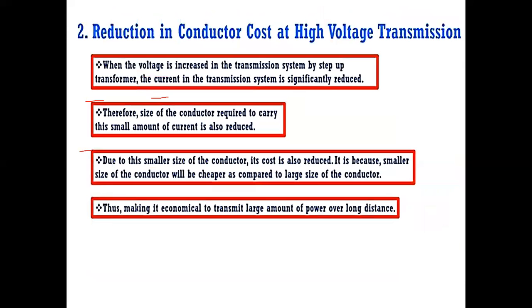Now the second point, the reduction in the conductor cost at high voltage transmission. When the voltage is increased in the transmission system by a step-up transformer, the current in the transmission system is significantly reduced. Therefore, the size of the conductor required to carry this small amount of current is also reduced. Due to this smaller size of conductor, its cost is also reduced. It is because a smaller size of conductor will be cheaper as compared to a large size of conductor, thus making it economical to transmit a large amount of power over long distance. Okay, we will discuss the rest of the points in the next video. Thank you.